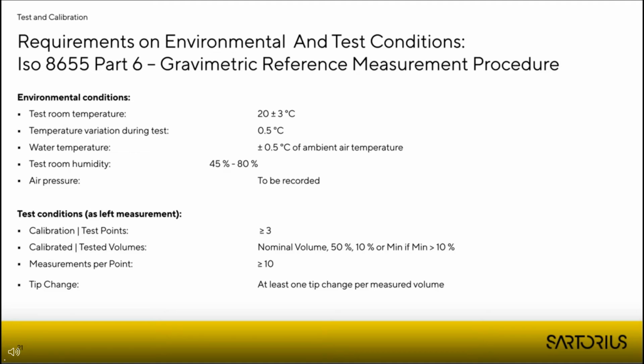The test room humidity, here we do have a much stricter requirement than in the old ISO. The test room humidity must be between 45 and 80% relative humidity. And last but not least here, the air pressure. For the air pressure, no specifications are given. It just needs to be recorded during the calibration.